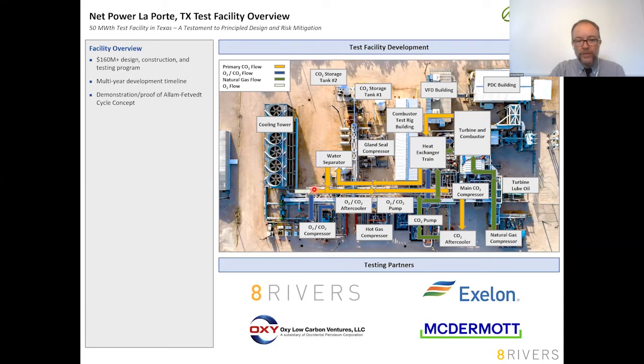We bleed a small part of it out and mix it with the oxygen, so we make artificial air - about 20% by mass oxygen, the balance being CO2. We put that back in through separate channels in the heat exchangers, and it works its way back up into the turbine combustor. We do this so that we do not have to have oxygen rated equipment on site, and because we are putting the oxygen back through the heat exchanger train, we do not want to worry about the inherent dangers of high temperature, high pressure, pure oxygen. So we make artificial air and run it back up into the heat exchangers and into the combustion turbine.